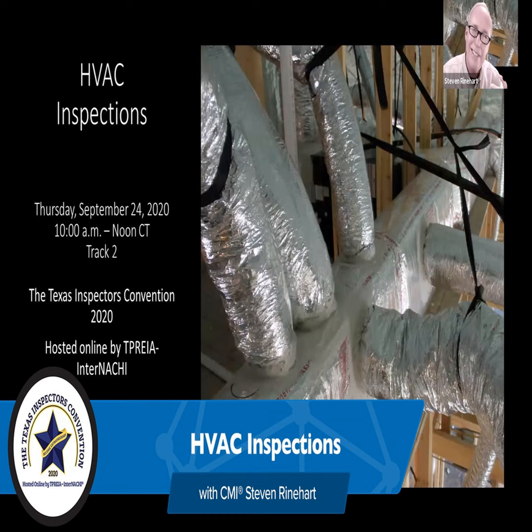I put in the report, even though it says looking at the coils were accessible, I make it known that they were not accessible. So I don't know the condition of the coil. And if the seller couldn't provide you any maintenance, and this house is 25 years old, it might be worth getting somebody to come look at that coil, because they will get very dirty.